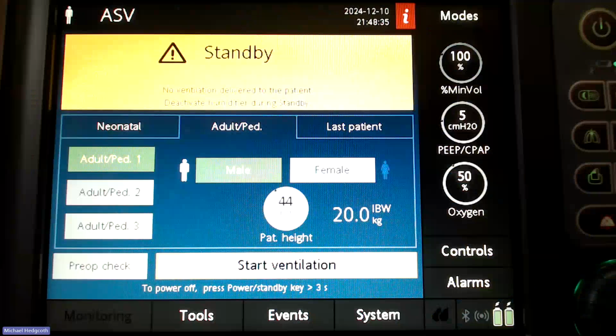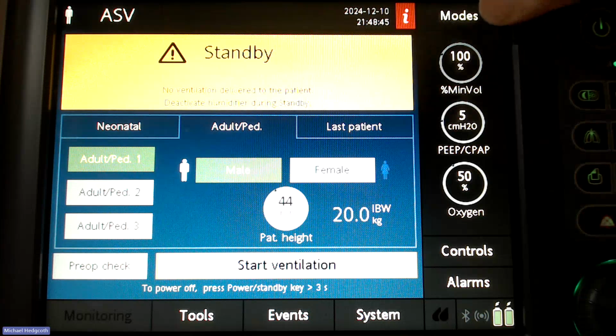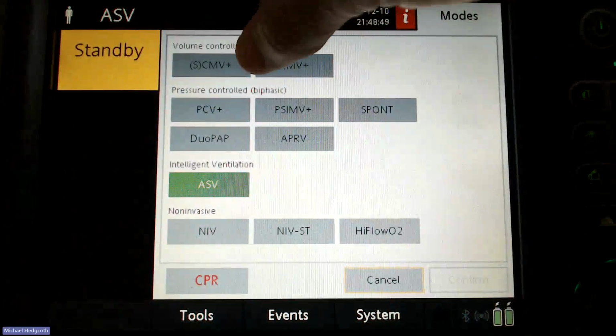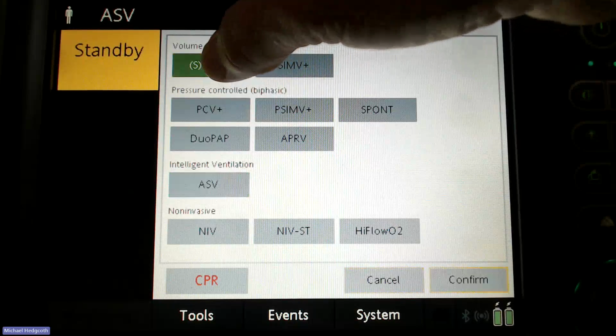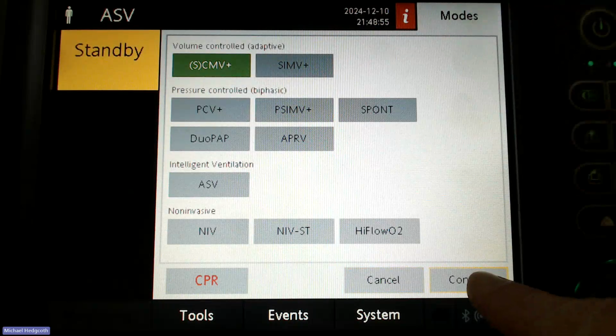But this will be your setup for patients 10 kilograms to 3 kilograms on the Hamilton C1s that you guys currently have using the adult peds tab. Once that's set up, you're going to connect the interface that you'll be going to the ET tube with, and then your ET tube and your pediatric patient connection. From there, on the actual C1, I'm going to jump over real quick. And hopefully you guys can see everything okay. Once we're set up, we're going to go into the modes. And I'm going to choose a volume mode. We could do pressure as well, but just to demonstrate the compensation for the tab, we're going to confirm.